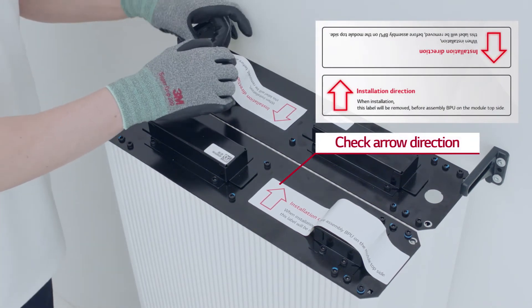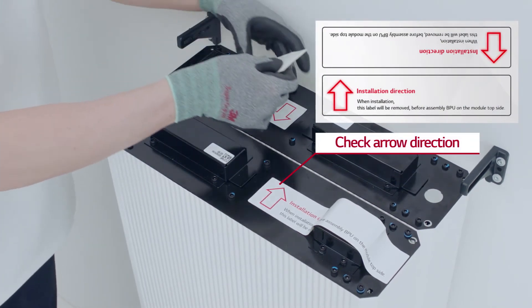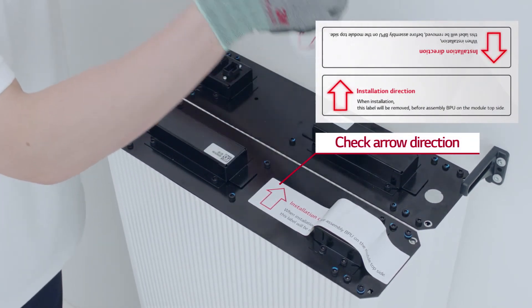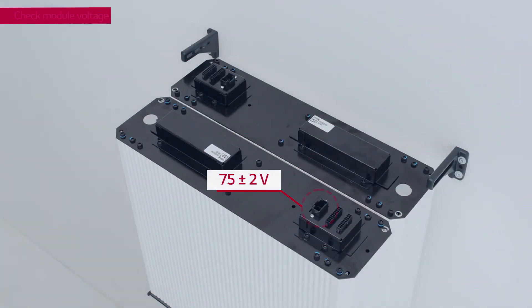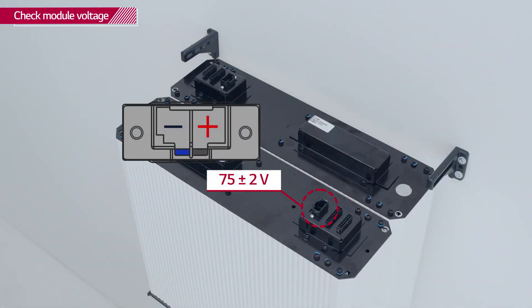Check that the arrows on the connector labels are displayed in the same direction as in the manual and remove the labels. With a voltmeter, check that the module voltage is within 75 plus minus 2 volts range.